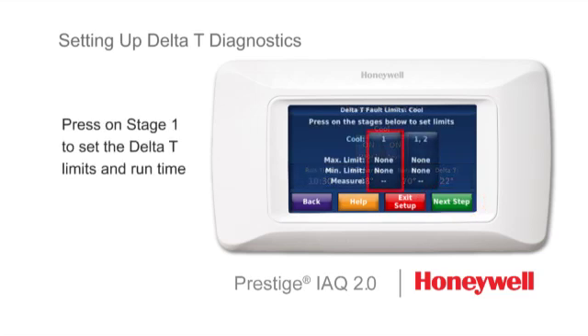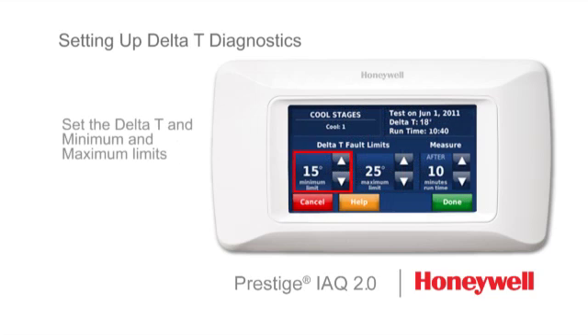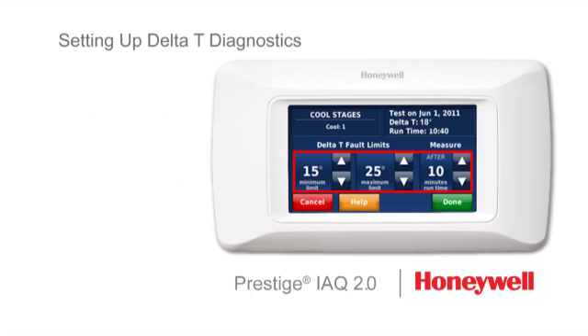Press on stage one to set the Delta T limits and runtime. Set appropriate minimum and maximum Delta T limits based on the Delta T reading from the equipment test and what you consider to be unacceptable system performance. Select a runtime when Delta T began to stabilize during the equipment test. When the thermostat is controlling the system, it will compare Delta T to the minimum and maximum limits after the equipment has run for this length of time.